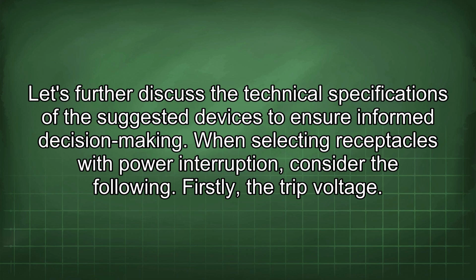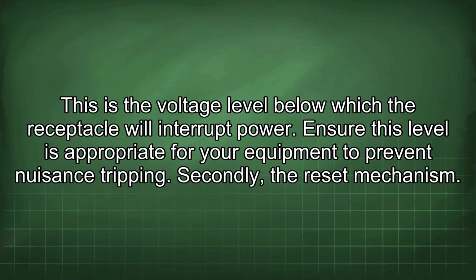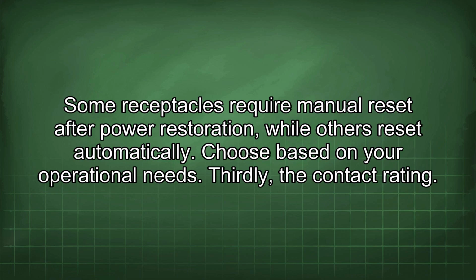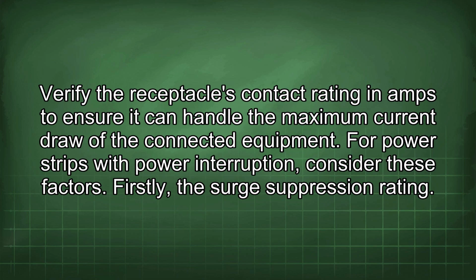When selecting receptacles with power interruption, consider the following. Firstly, the trip voltage. This is the voltage level below which the receptacle will interrupt power. Ensure this level is appropriate for your equipment to prevent nuisance tripping. Secondly, the reset mechanism. Some receptacles require manual reset after power restoration, while others reset automatically. Choose based on your operational needs. Thirdly, the contact rating.